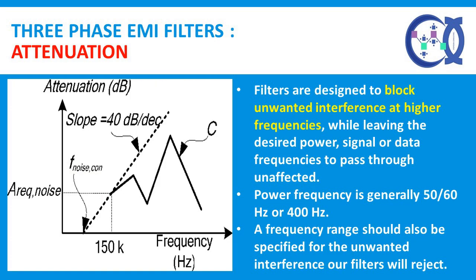Attenuation or insertion loss is a crucial parameter for defining the filter. Filters are designed to block unwanted interference at higher frequencies, while leaving the desired power, signal, or data frequencies to pass through unaffected. In the case of power line filters, the power frequency is generally 50, 60 hertz or 400 hertz, and only filters that match the designated frequency of your system should be used. A frequency range should also be specified for the unwanted interference our filters will reject.